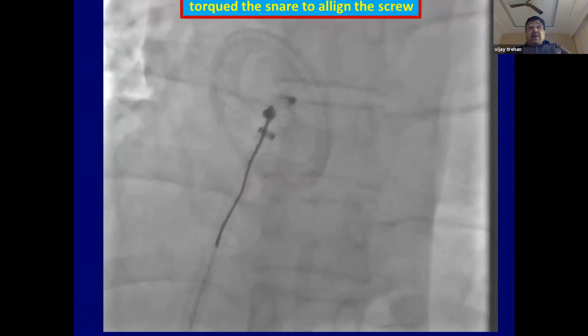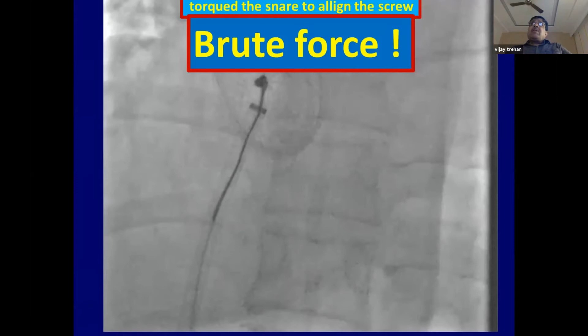In fact, what is happening is the sheath is trying to shorten. Brute force is being applied. Now, with this brute force, at times you are possibly able to retrieve the device, but very often this will result in either damaging the tip, but surely damaging the shaft of the sheath. What happens is, with this brute force, if you have a braided device, this will not shorten.